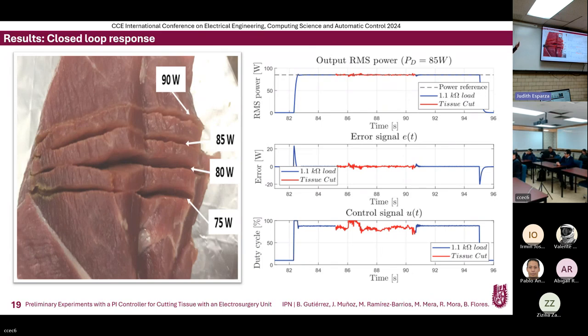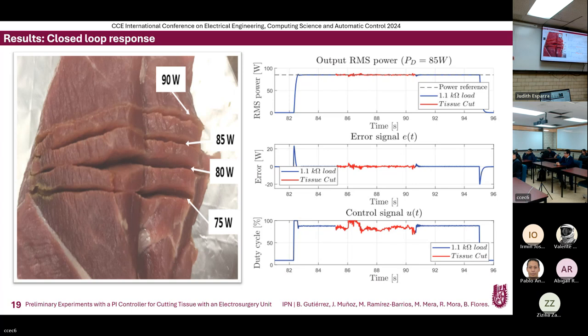These are other cuts using higher powers of 75 and 85 watts. You can see another graph of the power control using a reference of 85 watts. The blue line is again our 1.1 kilo-ohm load, and the red line shows the disconnection of that load and connection of the tissue while cutting. The PI control still regulates the power to the reference value.